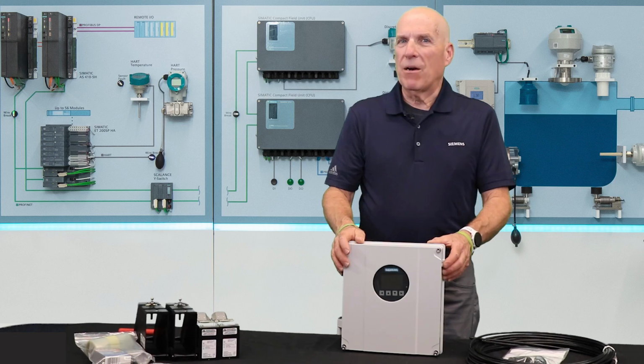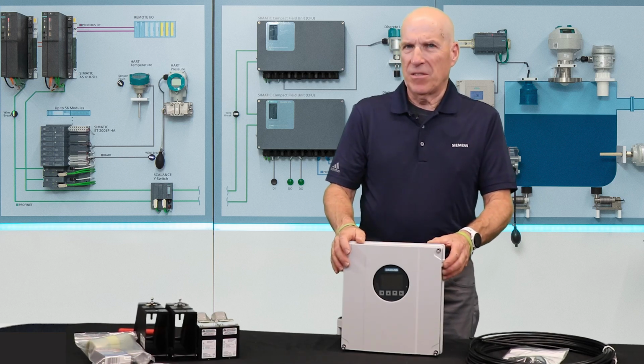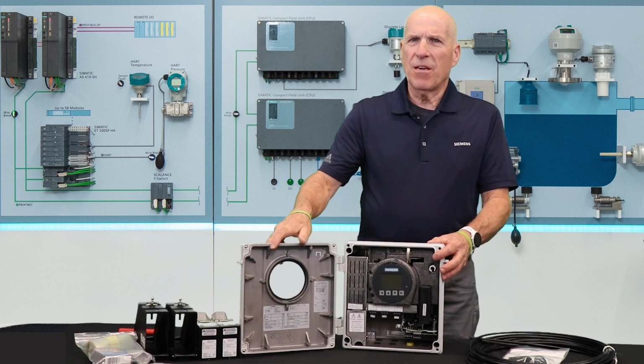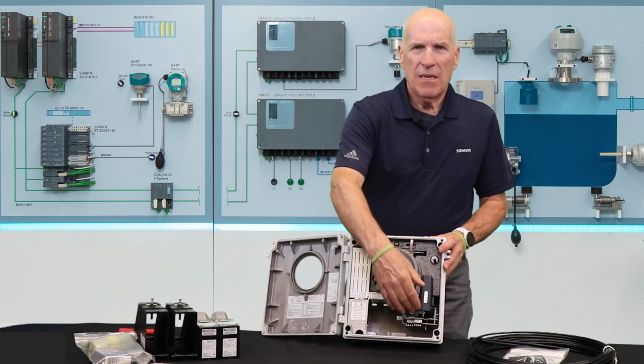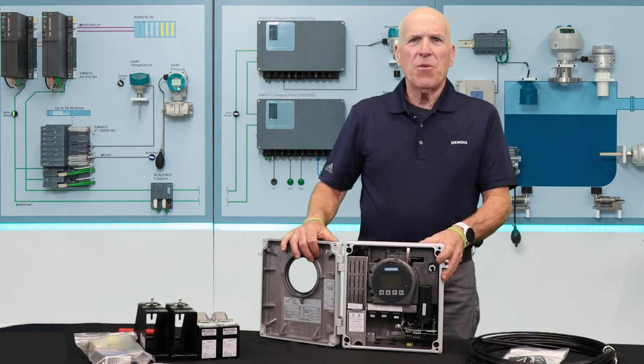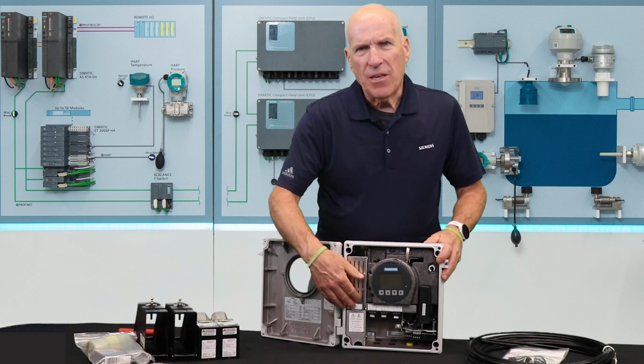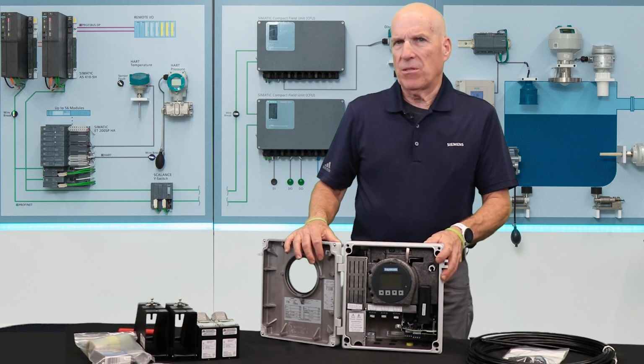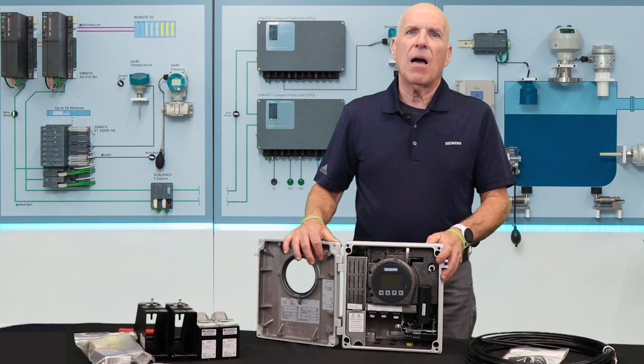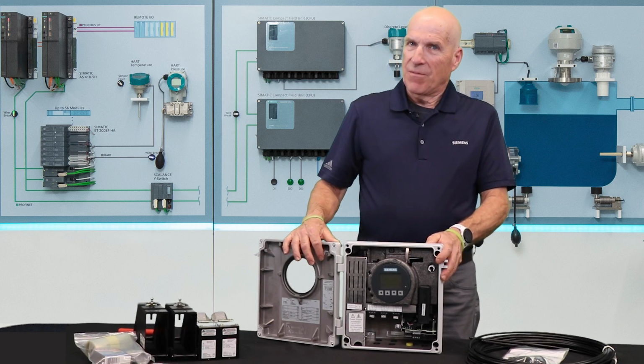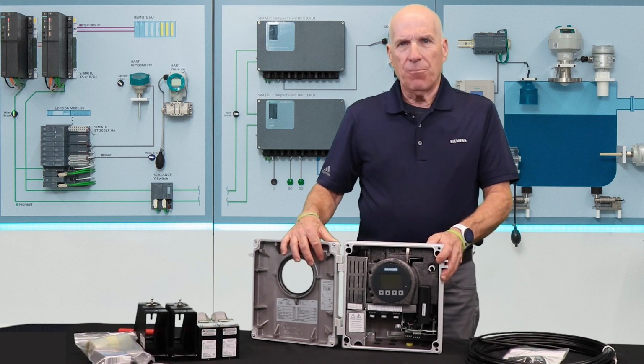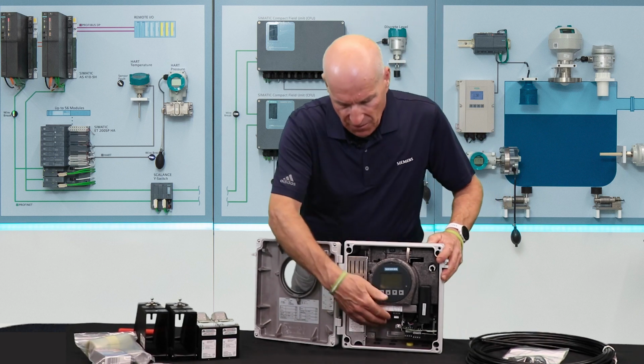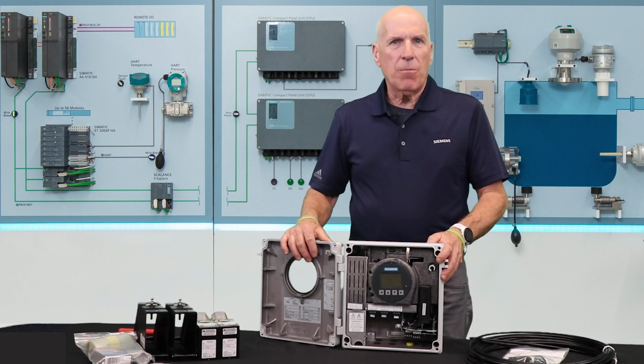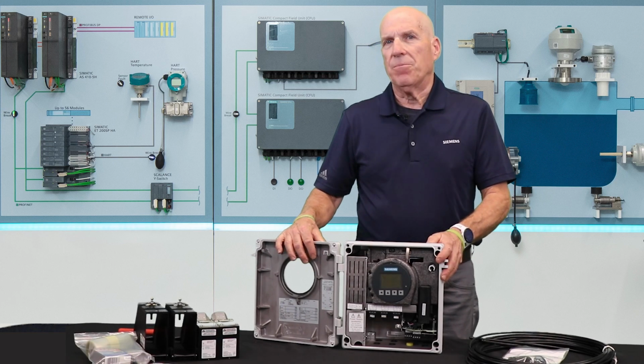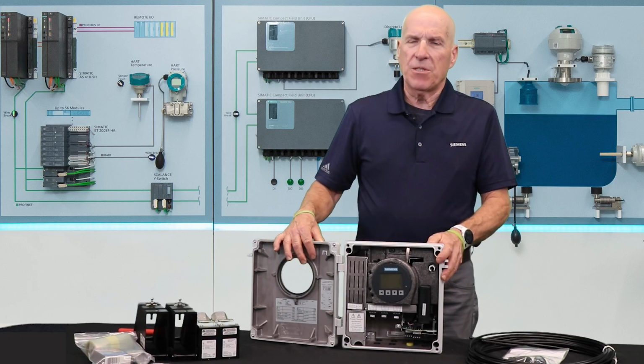The FS230 wall mount transmitter is by nature a dual path system. If we open the door, you'll see there are 2 sets of connections for your flow sensors down here, even if you've only ordered 1 set of sensors. It also offers dual power options so that you can use either AC or DC power source. And depending upon the choices made at the time of ordering, there's connectivity for multiple outputs, inputs, and communications, found here. Again, the system label provides information on how your transmitter is configured. We'll be breaking it down as we proceed.